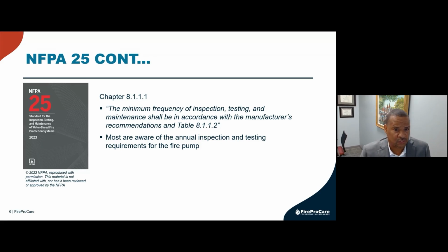And I want you to notice the key words on this slide. "Shall be in accordance with the manufacturer's recommendations and Table 8.1.1.2." I'll show you Table 8.1.1.2 in just a second, but it is so critical that you talk to the manufacturer, and that is the biggest gap I've seen in our industry.